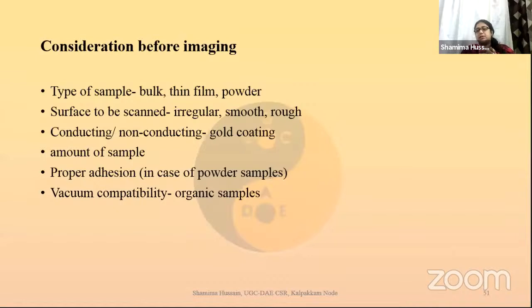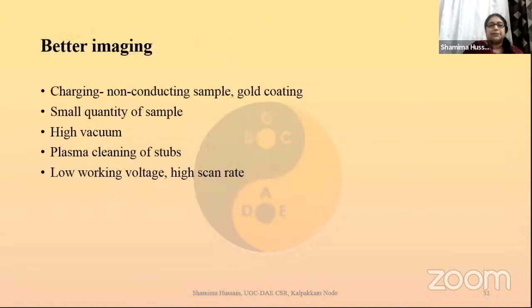Usually, whenever we are getting samples, in SEM we do not have insulators, semiconductors, and conductors. Here we distinguish our samples into two parts, insulators and conductors. If a sample is not conducting, it is insulating. That's all. There cannot be a semiconductor division there, because if I take something as a semiconductor, it will spoil the sample. So how do I make them conducting? We usually do some kind of gold coating. We can have a gold coating, or sometimes we also do carbon coating, based on what sample you have. That is how we make the surface conducting. If the sample is well conducting, then we have no fear of having the electrons on the surface, and they can go down beyond that. For better imaging, we need to have this gold coating.